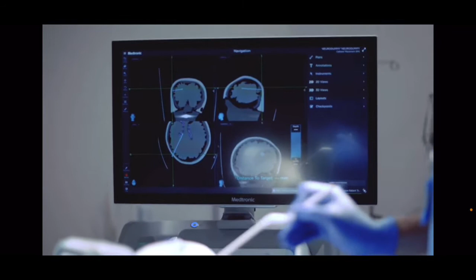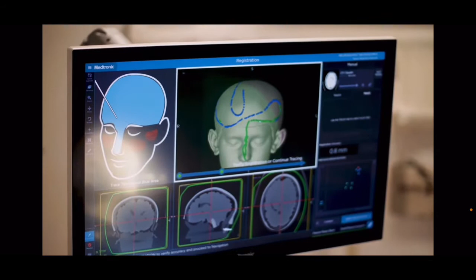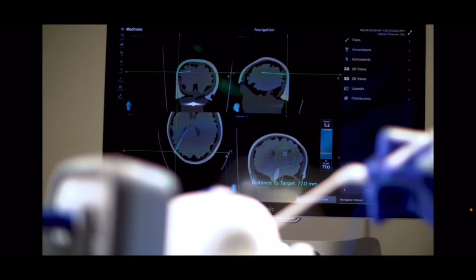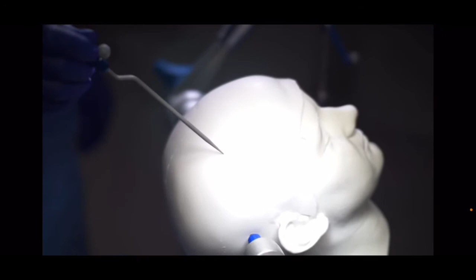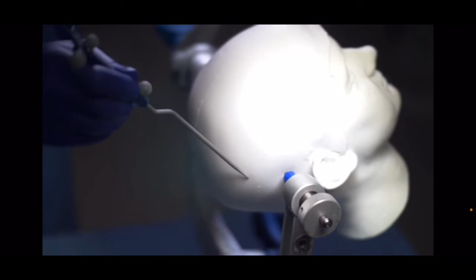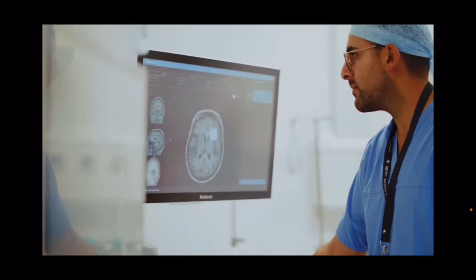For the software to display the instrument's location in relation to images of the patient, you've got to help the software by creating a map between points on the patient and points in the images. This process is called registration, and it's essentially the same for both optical and electromagnetic types. After registration is complete, whenever the surgeon touches a point on the patient using one of these tracked instruments, the computer uses the map to identify the corresponding point on the images. This identification is called navigation, and now I'm going to show you both systems in action.